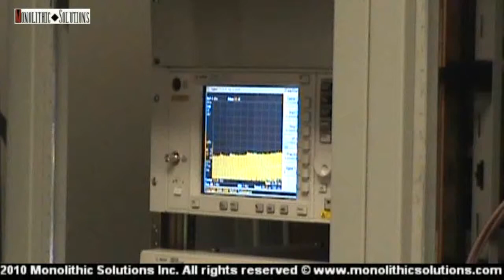This rack also includes the power distribution of the system. This is a 30 kVA PDU that provides abundant margin for the power requirements of the system. It also provides the power control, which includes system startup and system shutdown for the system. The PDU is responsible for gracefully shutting down the system to eliminate disk errors. It also sequences the shutdown and startup sequence with delays to minimize the abrupt power glitch. The PDU is backed up by an uninterruptible power supply.